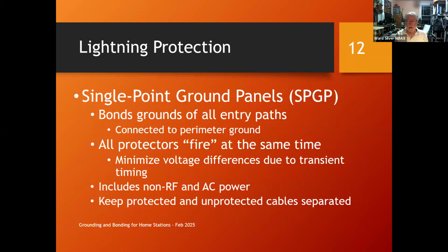Let's talk about this single point ground panel. The whole point is to bond all of the grounds of all your entry paths - all your feed lines, rotator control lines, power stuff. If you can also include your data service, telephone service, cable TV, whatever, on this panel, that's so much better, because all the grounds are bonded together in one electrically small volume, and then you can connect them to whatever ground system you have.